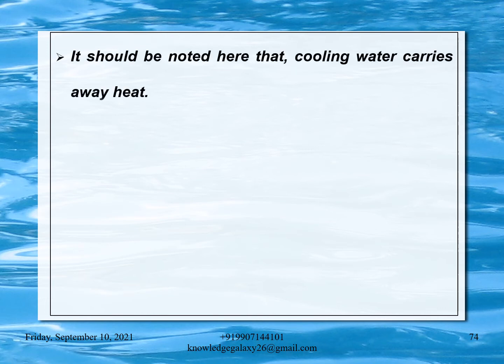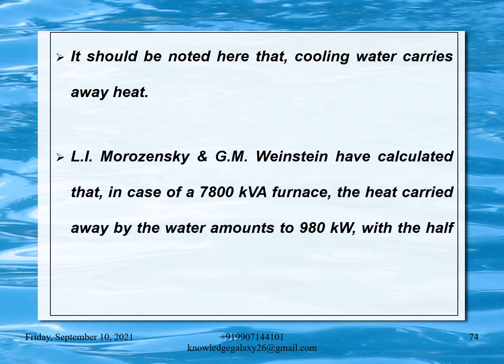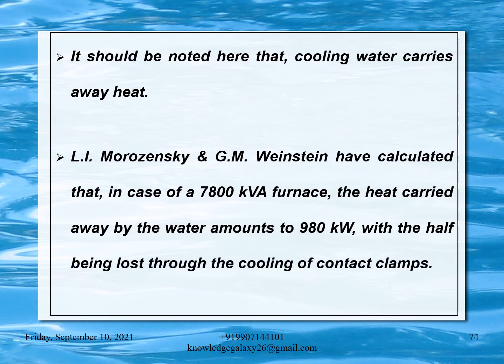It should be noted here that cooling water carries away heat. L.I. Morozensky and G.M. Weinstein have calculated that in the case of a 7800 kVA furnace, the heat carried away by the water amounts to 980 kW, with half being lost through the cooling of contact clamps.